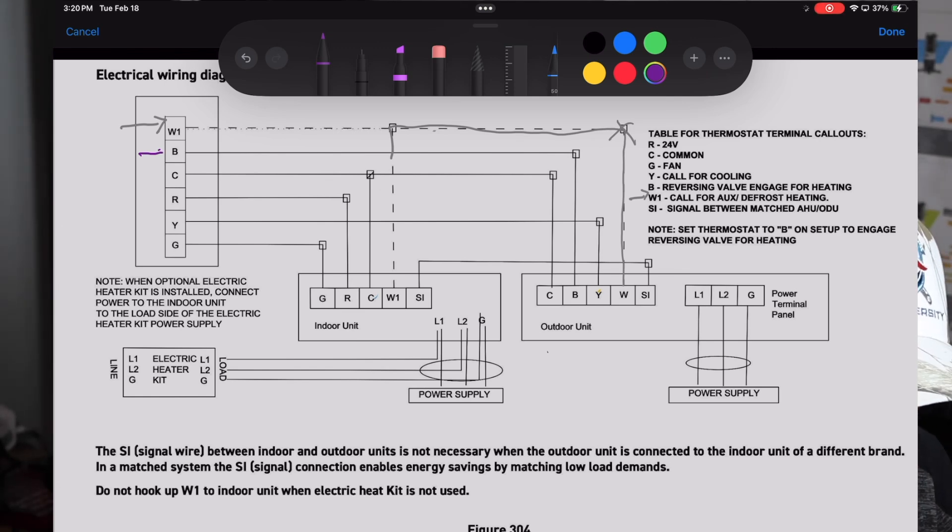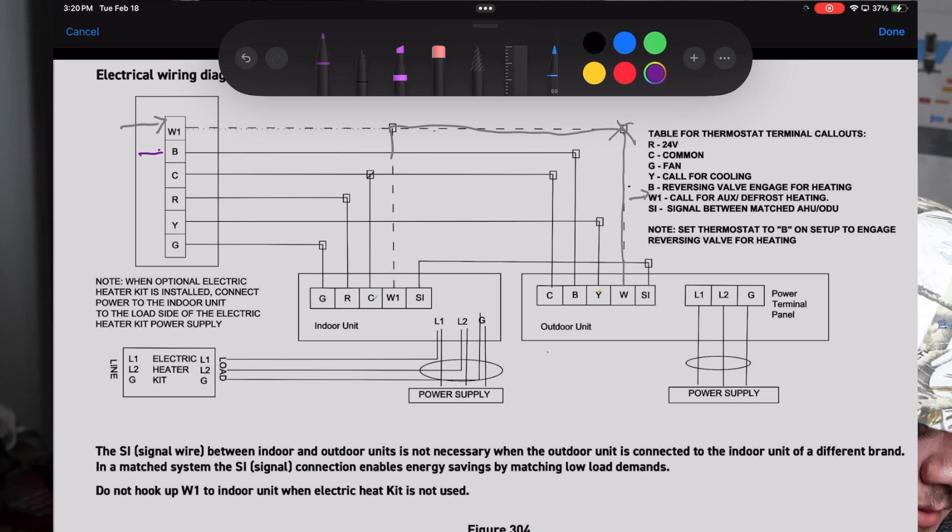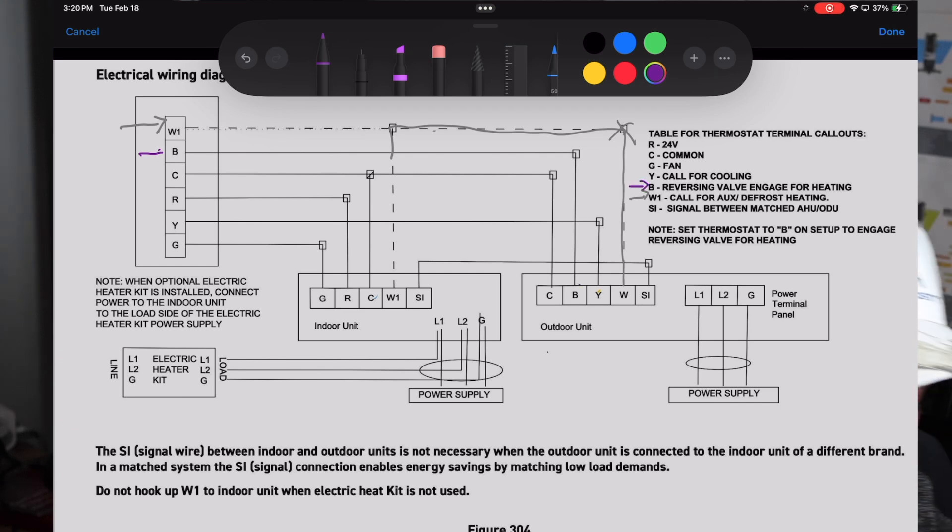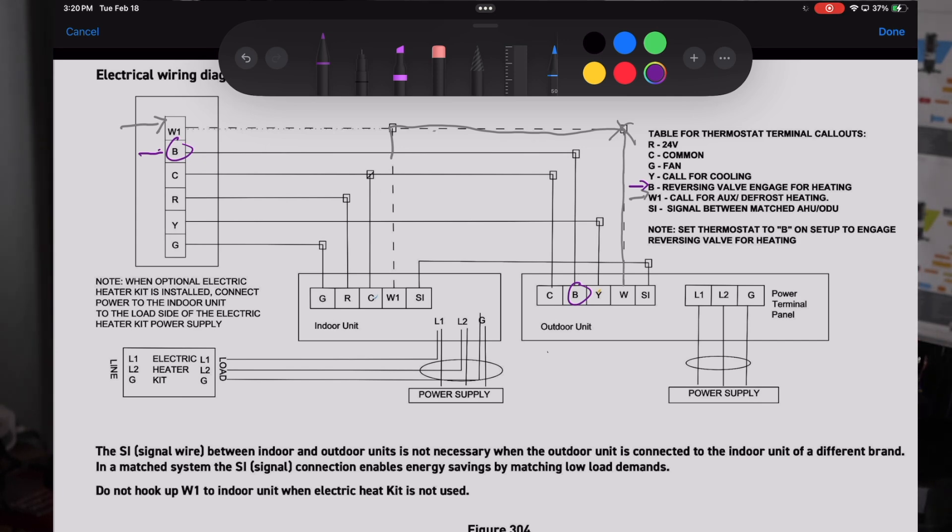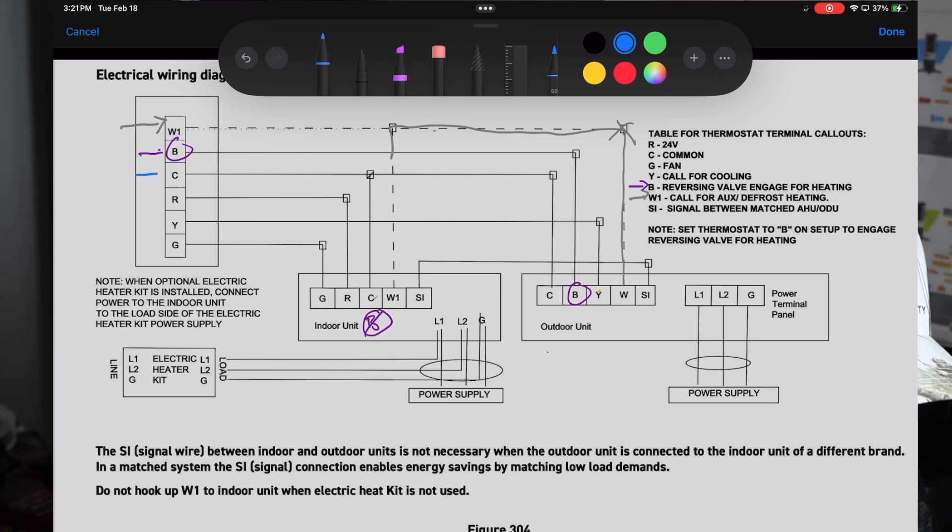Running down the line, the very next terminal is our B terminal. The B terminal is our reversing valve that is energized in heating. A lot of people are used to the O terminal which is energized in cooling and fails in heating. For this unit specifically, we are energizing in heating and failing in cooling. So make sure you set your thermostat up accordingly for the B terminal and not the O terminal.